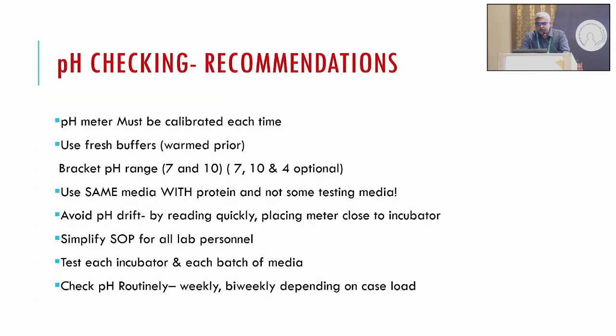So the recommendations. How you check the pH is just as important, and how it should be performed. The pH meter should be calibrated each time. It shouldn't be calibrated only once in a month or so. It should be calibrated every time you take a measurement, using fresh buffers which are warmed beforehand, ideally at 37 degrees.